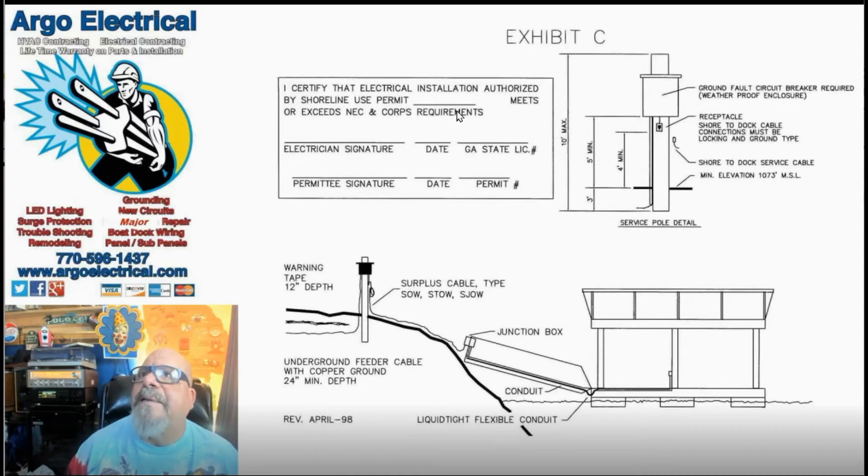As shown here, this is on the shoreline — you'll have a little sub-panel here with at least one 20-amp ground fault circuit breaker, and then there would be a receptacle here that protects the power to the dock. You can see that is at a four-foot minimum, the top of the panel at a five-foot minimum. A good rule of thumb is the middle of the panel should be at about 60 to 64 inches tall.